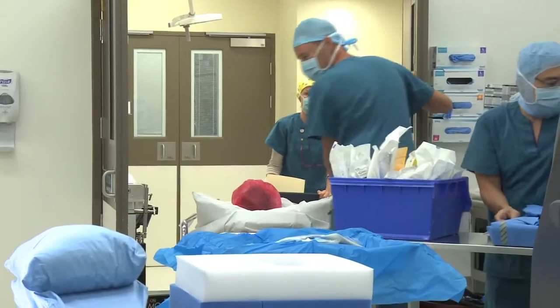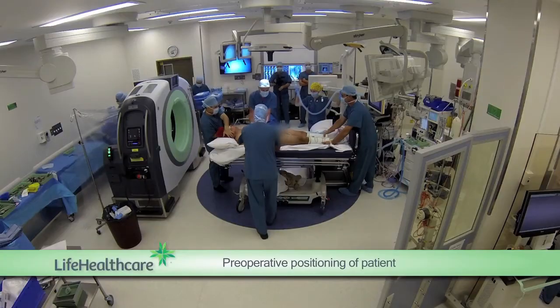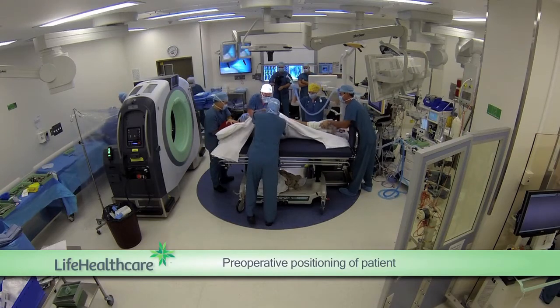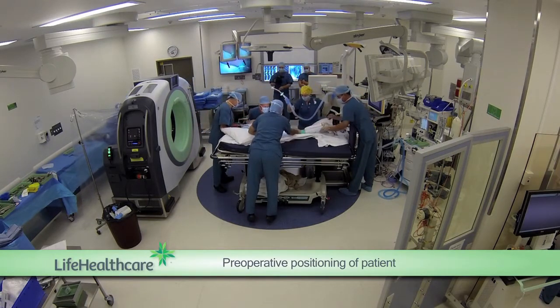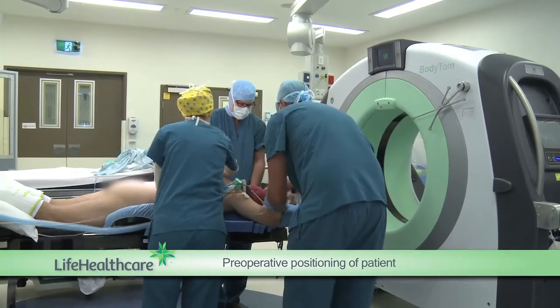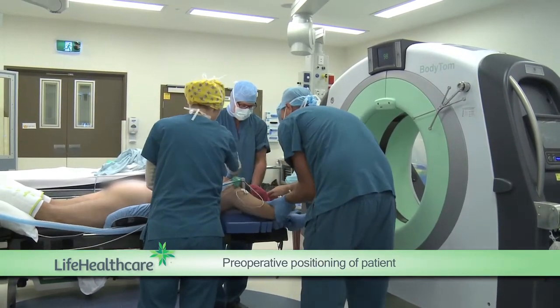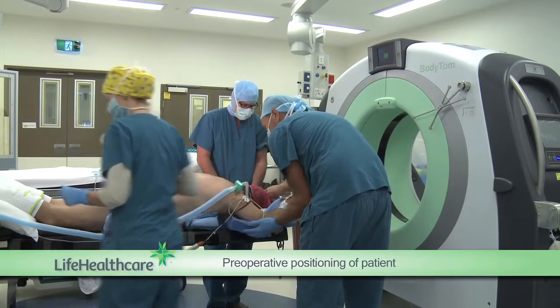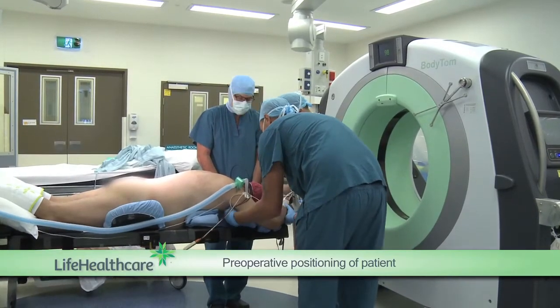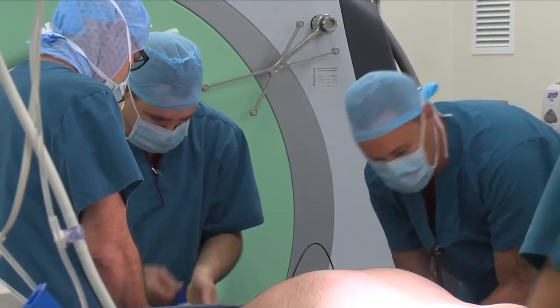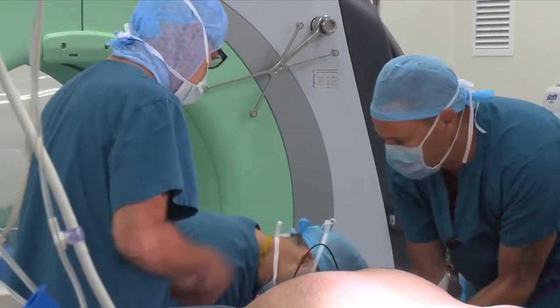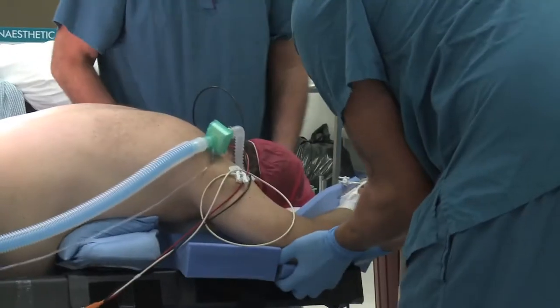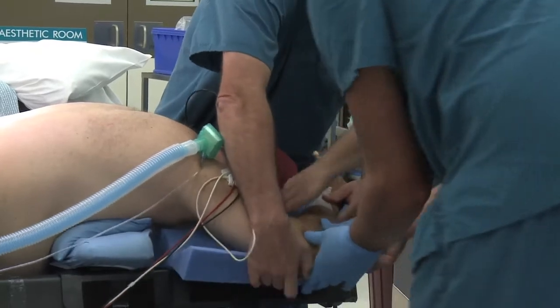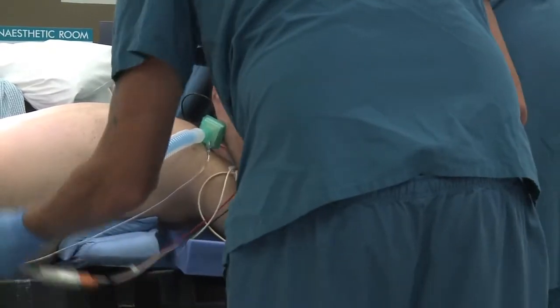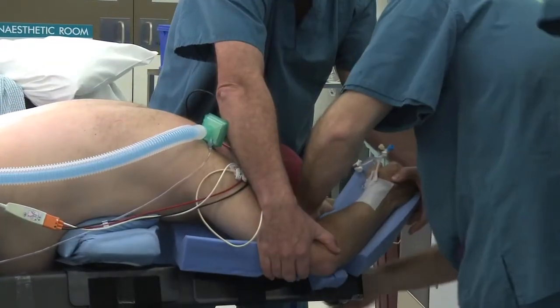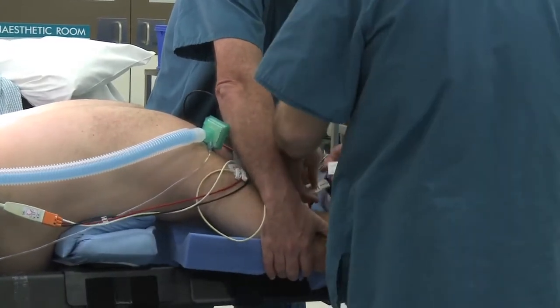Once the warm-up and calibration has been completed, the patient can now be brought into the theatre and positioned correctly on the table. In this instance, the patient is placed prone on the table with the head towards the gantry. The arms can be placed in various positions. Both arms above the head, as in this case, one hand above the head and one down by the side, this is called the swimming position, or both hands by the side. All of these positions enable the gantry to move smoothly over the patient without obstruction.